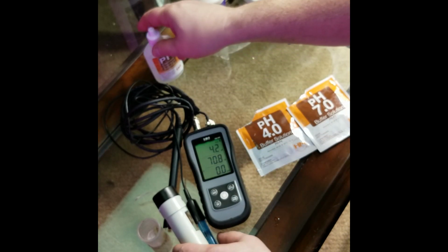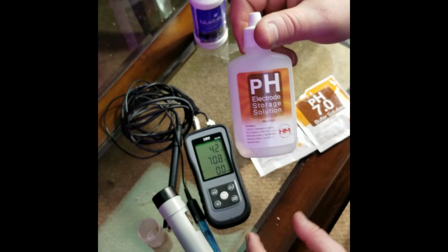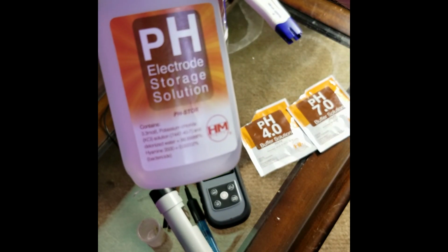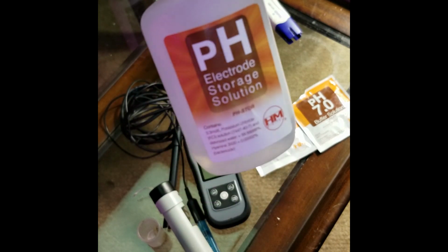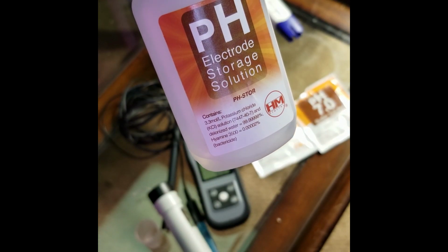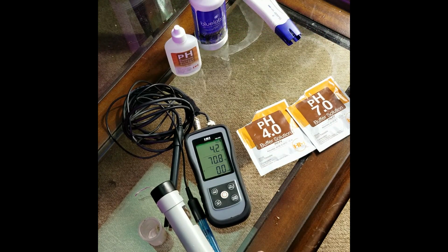and that is because the more ppm you have in potassium chloride, or the more everything you've got basically in the solution, the less the water is going to try to pull from the meter, from the glass, from the probe, from the ions, causing it to more prematurely wear out.